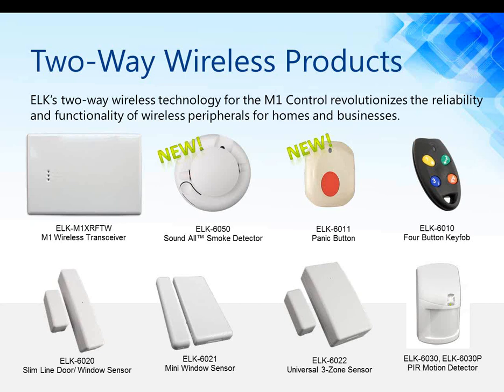Sure. We are very excited about our Sound All smoke detector. It is a unique smoke detector in the two-way line. One of the unique features of that smoke detector is the Sound All feature, and of course that's why it's in the name. What that means is that if one of these smoke detectors goes off, or if you just have a fire alarm event on the system, through the two-way it's able to activate the built-in sounder on all of the enrolled smoke detectors.